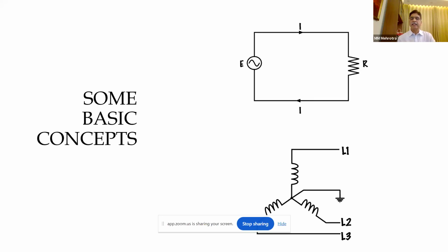I will also mention the earth conductor. What happens to the earth conductor? As per code, the earth conductor will be half the size of the main conductor, but with a minimum size of 1.5 square mm. Suppose for my point wiring I am using a 1.5 square mm conductor. My neutral wire will also be 1.5, and the earth wire will also be 1.5.